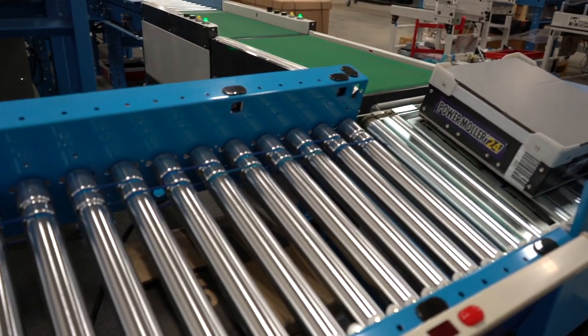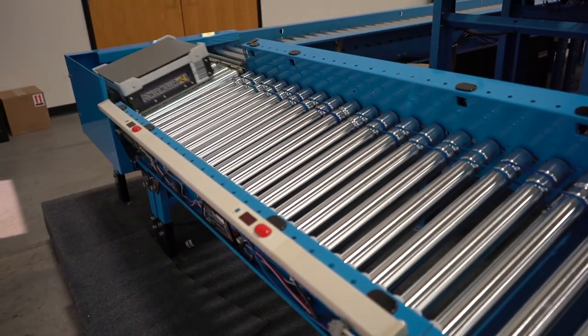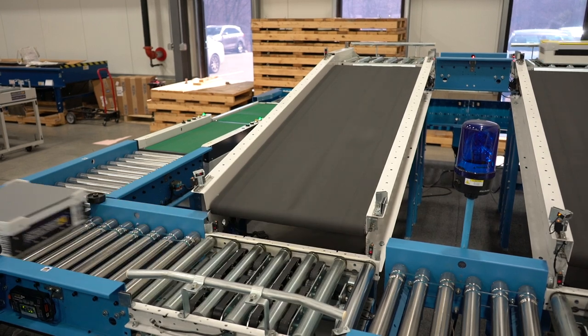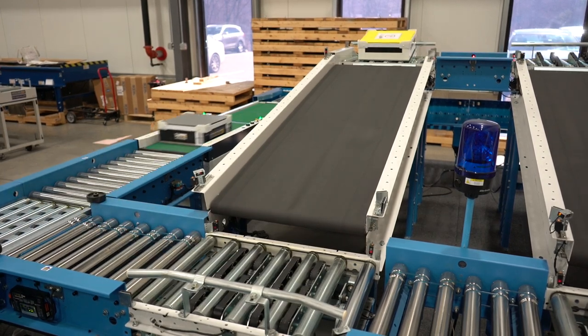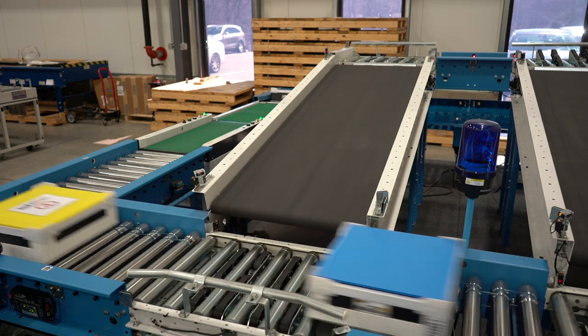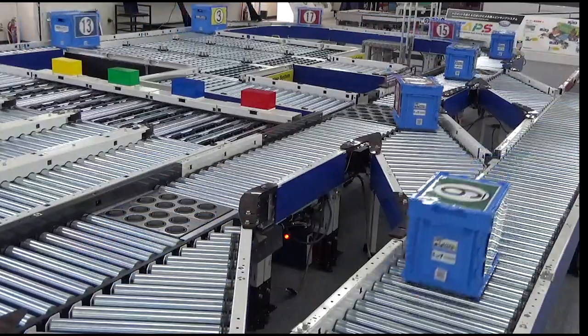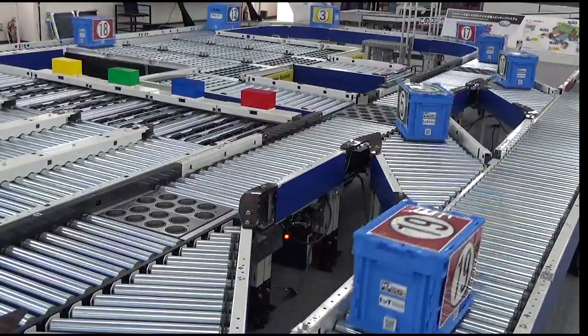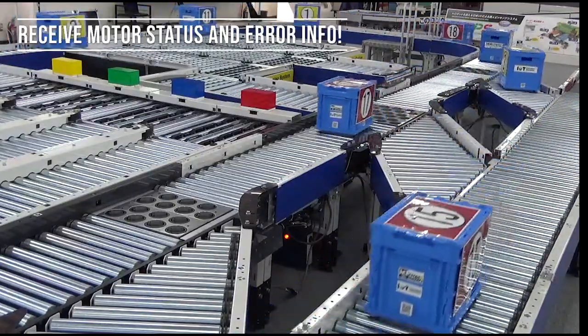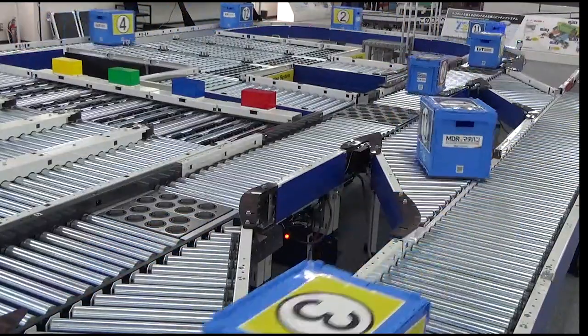Complete control is possible because settings can be entered via computer and then sent to the controller. The dual-zone platform allows for a reduced number of node IDs for longer single-network communications. Keep in mind that these communications are in both directions — the controller can receive start, stop, and speed changes over the network while sending back motor status and error information up to your upper-level platform if necessary.